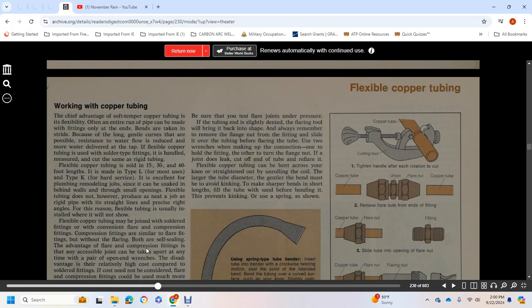Working with copper tube. The chief advantage of soft tempered copper tube is flexibility. An entire run of pipe can be made with fittings only at the ends, but bends are to be taken in stride. Because of the long gentle curves that are possible, resistance to water flow is reduced, and more water is delivered at the tap. Flexible copper tube is used with solder type fittings. It's handled, measured, and cut the same as rigid tube.